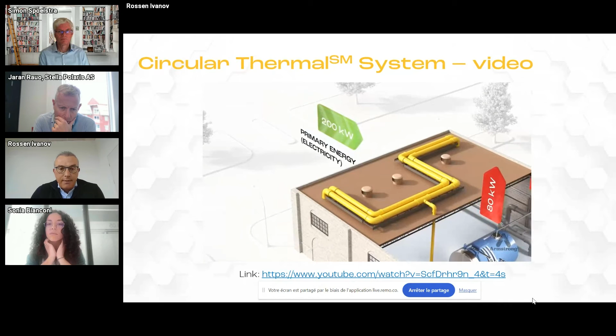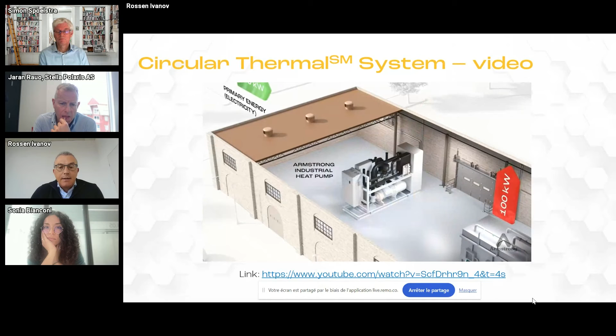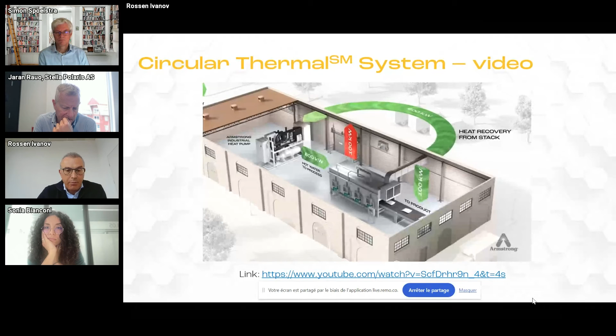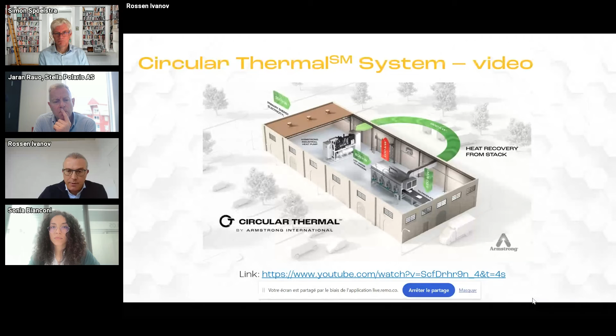The idea here is to apply circularity to heat, where we apply circularity to material and we apply circularity to water. This would mean recovering the low-temperature stacks and upgrading them to high temperature using heat pumps, as has been shown so far. And electrification also allows us to decarbonize if renewable electricity is being used. The impact is a significant reduction of primary energy, up to 80% in the food industry, which typically requires temperatures below 200 degrees centigrade, and often less than 100 degrees centigrade.